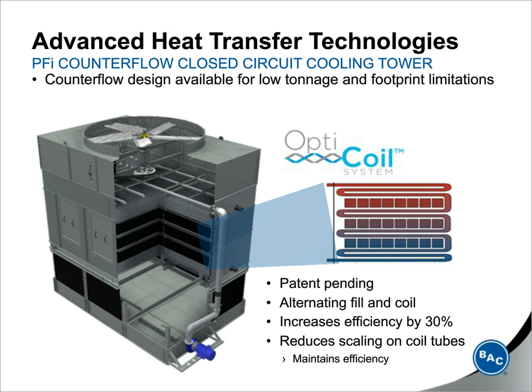This technology can actually reduce fouling by around 50%, since the majority of the evaporation occurs on the fill and not on the coil. And fill is much less expensive than the coil, and it's easier to access and to replace when necessary. Now, this will really allow you to operate the equipment at peak performance for a longer period of time. And again, as has been the theme throughout this presentation, this is going to reduce your total cost of ownership.